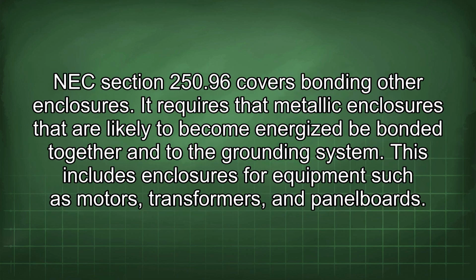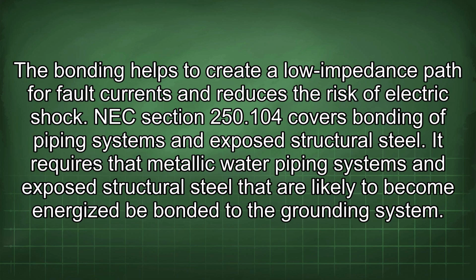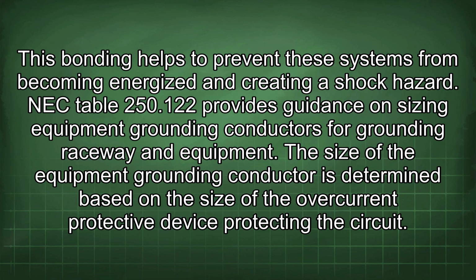NEC Section 250.96 covers bonding other enclosures. It requires that metallic enclosures that are likely to become energized be bonded together and to the grounding system. This includes enclosures for equipment such as motors, transformers, and panelboards. The bonding helps to create a low impedance path for fault currents and reduces the risk of electric shock. NEC Section 250.104 covers bonding of piping systems and exposed structural steel. It requires that metallic water piping systems and exposed structural steel that are likely to become energized be bonded to the grounding system. This bonding helps to prevent these systems from becoming energized and creating a shock hazard.